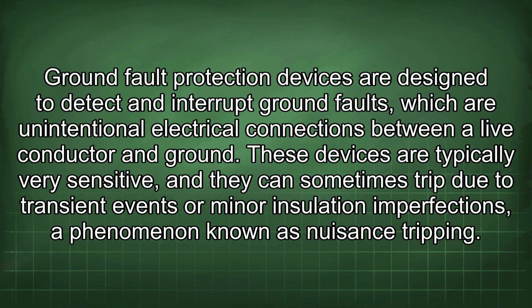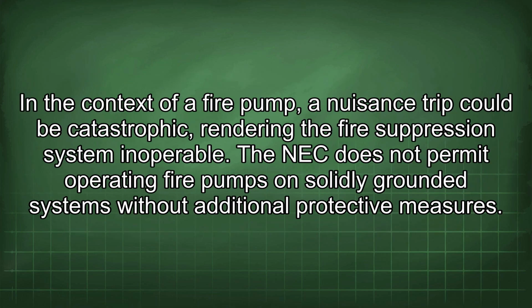Ground fault protection devices are designed to detect and interrupt ground faults, which are unintentional electrical connections between a live conductor and ground. These devices are typically very sensitive, and they can sometimes trip due to transient events or minor insulation imperfections, a phenomenon known as nuisance tripping. In the context of a fire pump, a nuisance trip could be catastrophic, rendering the fire suppression system inoperable.